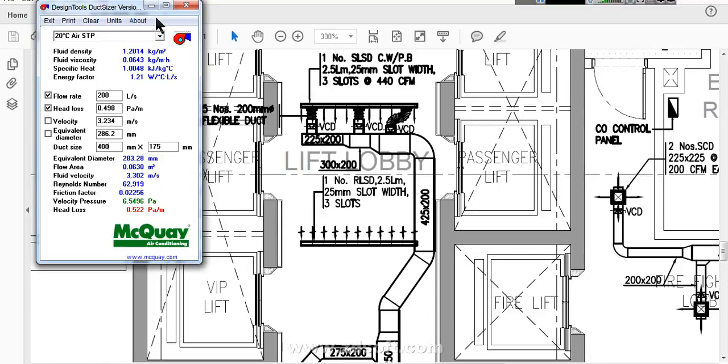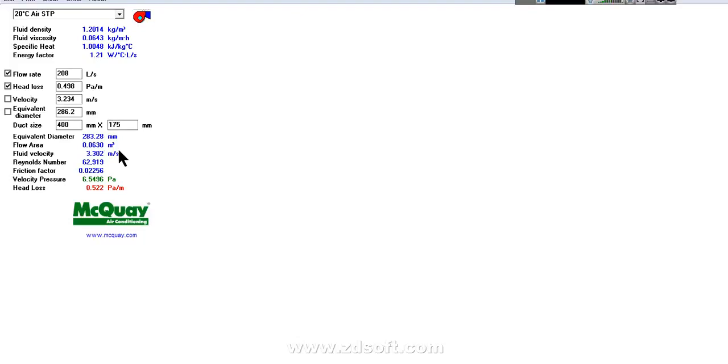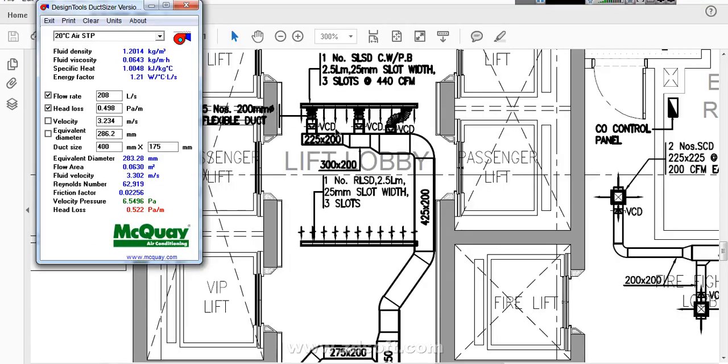Here you can see in this software, there is a velocity. Velocity should not increase more than 5 meters per second. If it is more than 5 meters per second, there is too much sound, noise will be there inside the duct. It should be for accommodation areas like bedroom or any other occupied area, the duct's velocity should be less than 5 meters per second, this is comfortable.